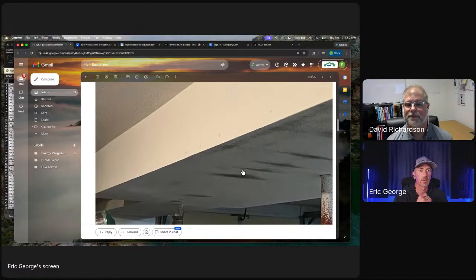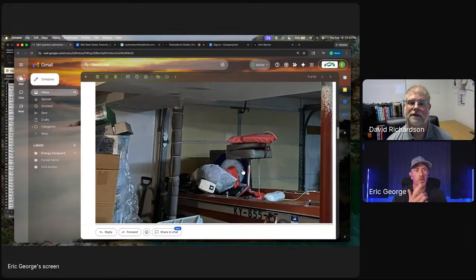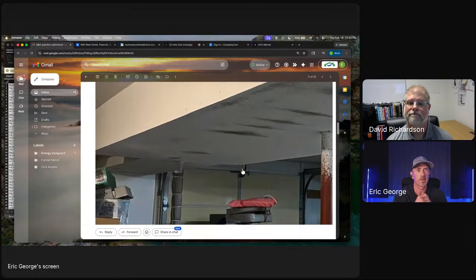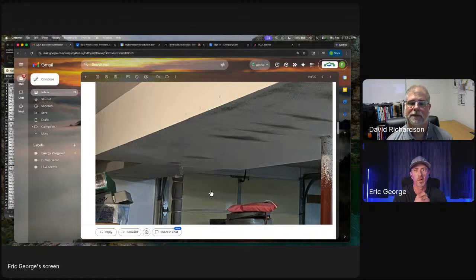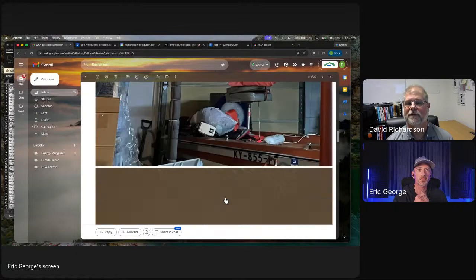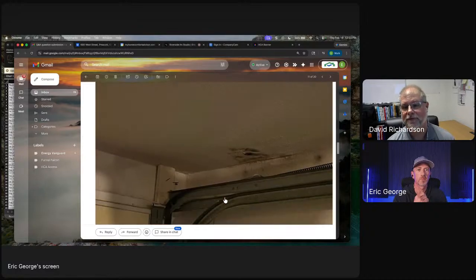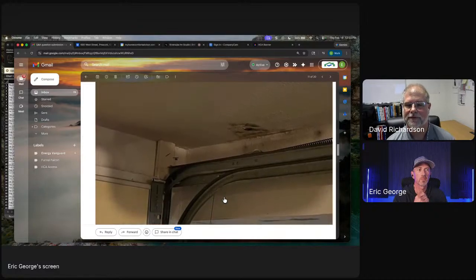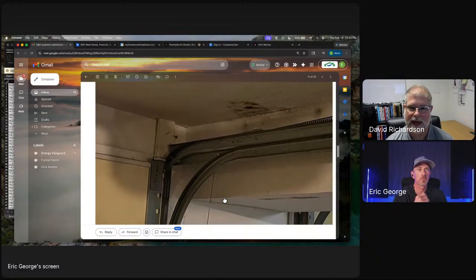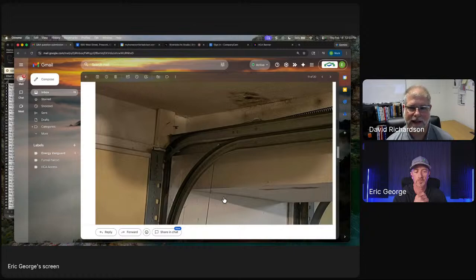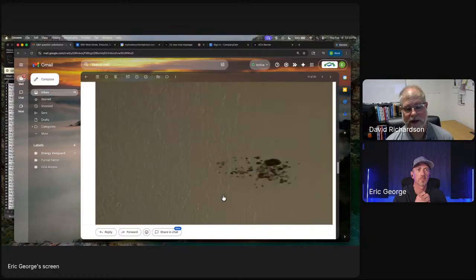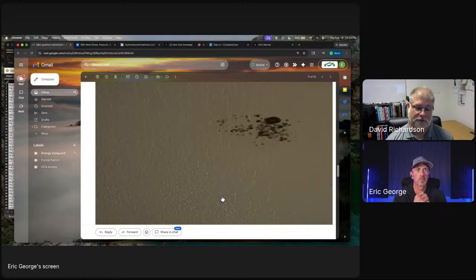Yeah, so his garage is kept open pretty much all summer, sounds like, from sports activities with the kids, and this is what's showing up on the drywall. So if that is indeed the M word, which would be hard to tell without measuring it, in the past summer that we had with such high dew points, any exposed metal or any duct leakage, the dew point of metal ducts or even flexible ducts, those will reach dew point and start to drip. So if it's showing on that side of the drywall, there's no telling what it looks like on the other side.